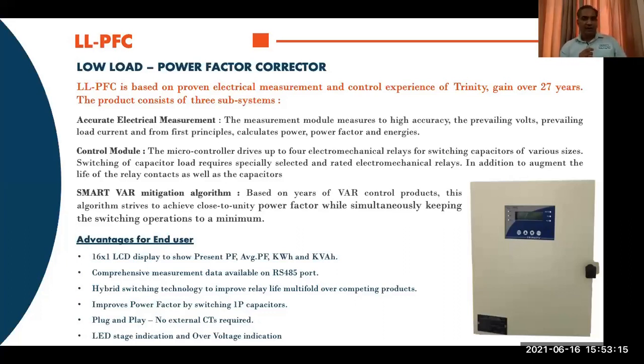We came up with this product called low load power factor correction panel, LLPFC as we call it. A 4 kVAR panel, as you can see, a small panel with our own controller, single phase, maintaining PF to 0.95, 0.98, 0.99, whatever best we can do on those small loads. We have sold not less than 500 such panels in the last 2 years, going out again and again to small clusters of people facing such problems because of this electricity board rule.